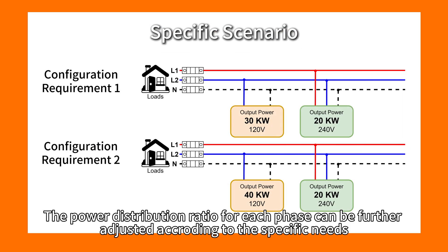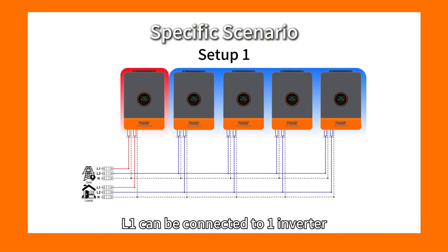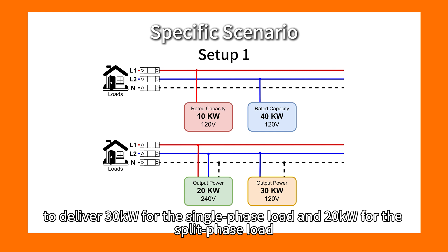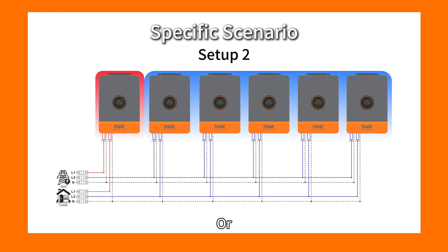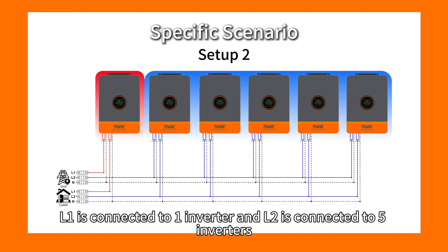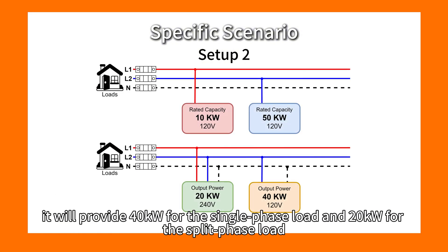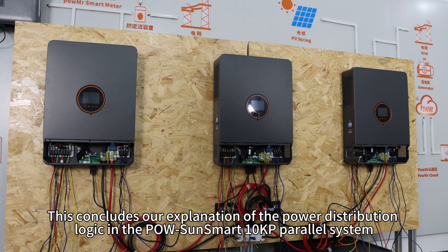The power distribution ratio for each phase can be further adjusted according to specific needs. For instance, L1 connected to one inverter and L2 to four inverters delivers 30kW for the single-phase load and 20kW for the split-phase load. Or with L1 on one inverter and L2 on five inverters, it provides 40kW for the single-phase load and 20kW for the split-phase load.